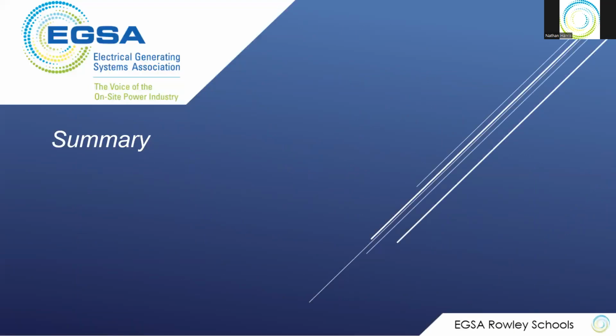So, quick summary. And Matt, to answer your question, are medium voltage machines harder to maintain? Not harder. Because of the voltage stress in there, you need to make sure they're kept clean, because a little bit of buildup of corrosion or a little buildup of dirt in the system can actually cause a fault in the machine. So they're not harder to maintain. They're usually built with different specifications.